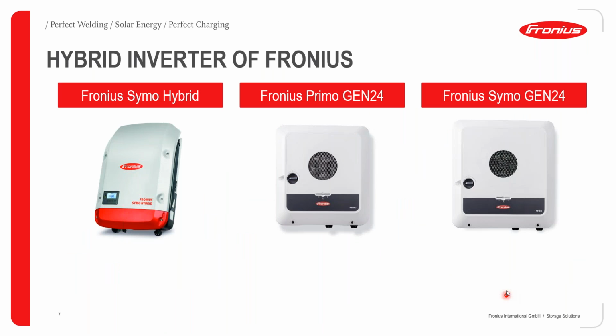Just to give you an overview of the different hybrid inverters from Fronius, starting off with the Fronius Symo Hybrid. This inverter is still in production and will still be in production for many more years to come. It comes in 3 size variants: 3 kilowatts, 4 kilowatts, or 5 kilowatts. It is a 3-phase inverter. It allows for direct battery connection, it has a single MPPT tracker, and it also allows for 3-phase full backup power.